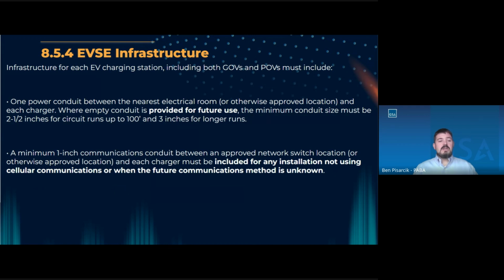Likewise for the communications conduit, a minimum of 1 inch communication conduit between an approved network switch location or otherwise approved location, and each charger must be included for any installation that is not using cellular communications or when the future communication method is unknown. In many of our cases, I would say over 90%, are using cellular. And if that's the case and you know that, then you don't have to install this extra conduit. But if you don't know, or in some cases you don't have cellular, then you do need to install it. And especially with underground parking, things like that, there is a place for it.